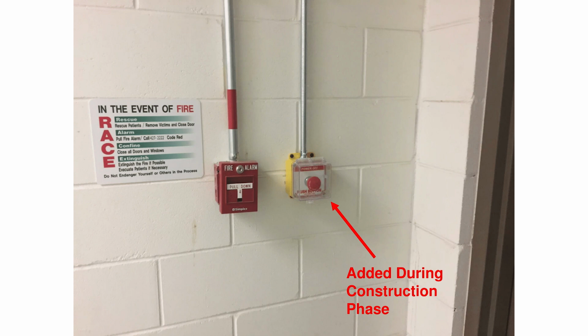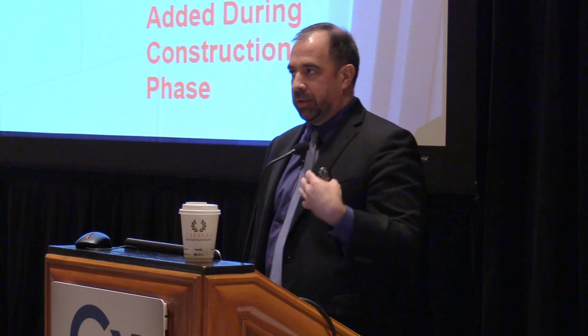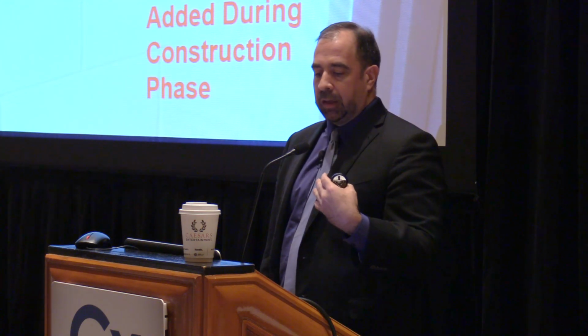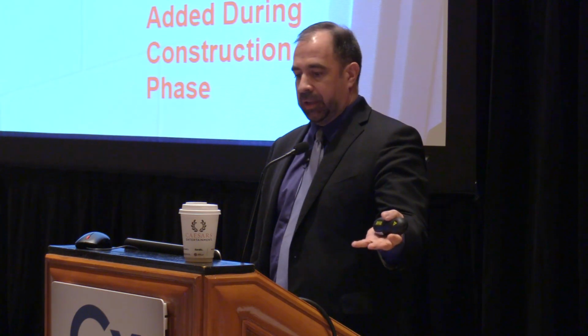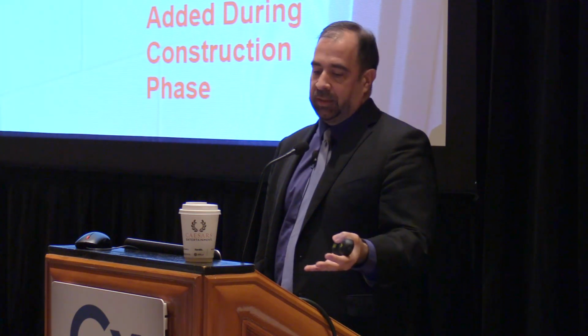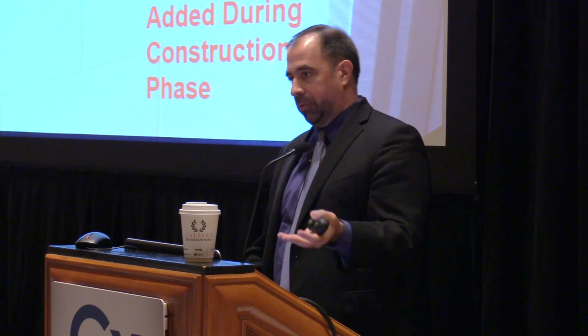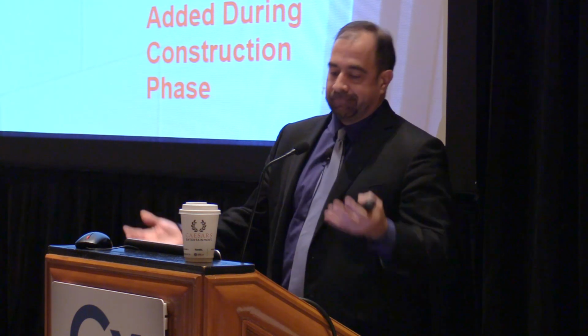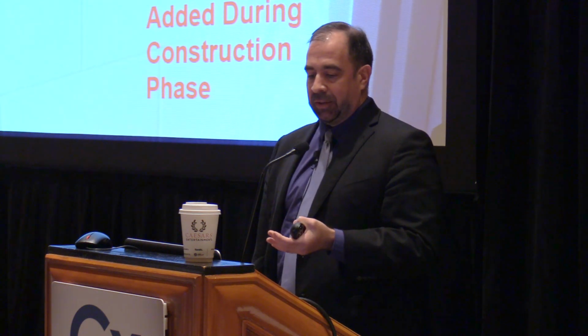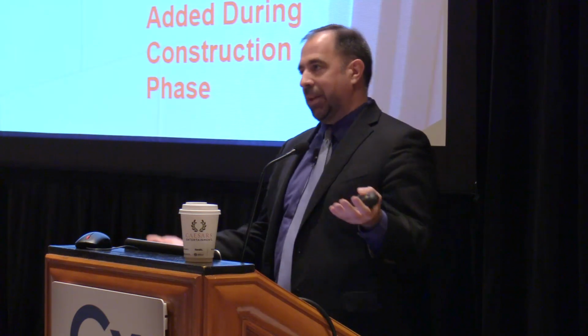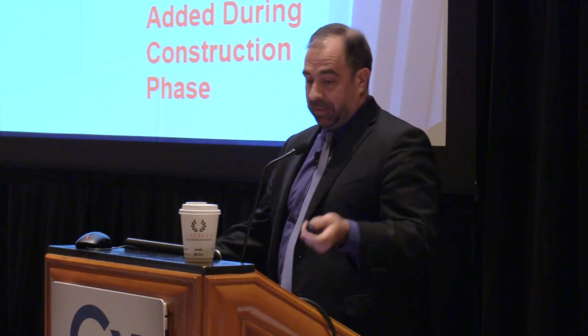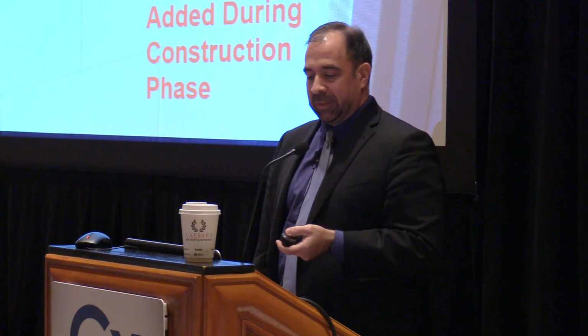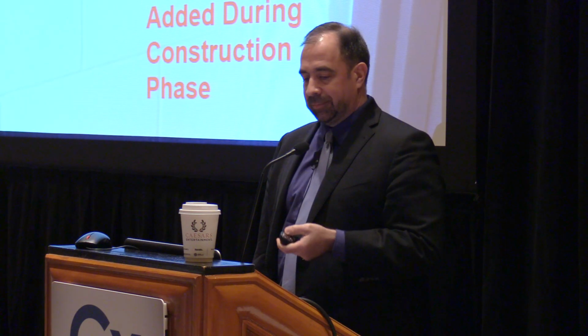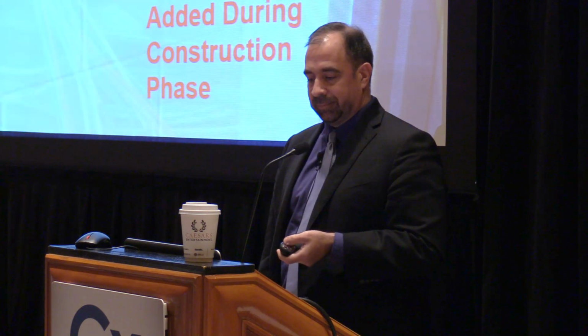EPO switch, emergency power off switch for the generator, is required to be outside the generator room. I'd like to think if I had reviewed the drawings during the design phase, I would have asked, hey, where's your EPO switch? They didn't have that, so when I got there during construction, I said, hey, where's your EPO switch? And they said, oh, that's a good question. So they installed one after, but later than it needed to be, and it was 3 RFIs and a whole thing.